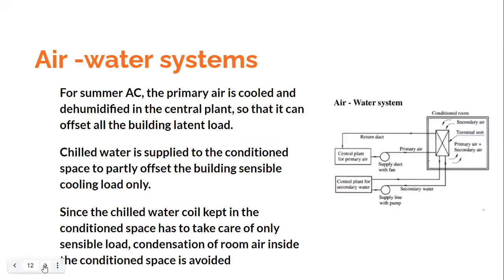And then many a time you would require to use both the fluids, that is the air as well as water. Those kinds of systems are called air water systems. Okay, so from the diagram it would be clear that you would have a primary air supply and you would have the secondary water supply. So primary air, look at this, there is a central plant which is going to cool the primary air. For example, in summer air conditioning, you need to cool and dehumidify in this, and then you need to take care of the latent load.